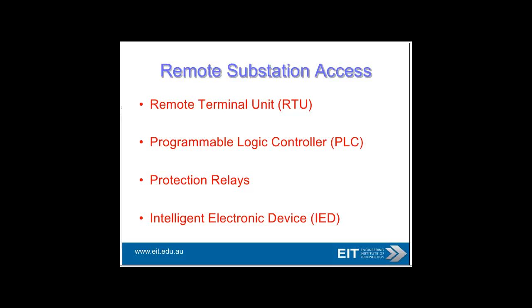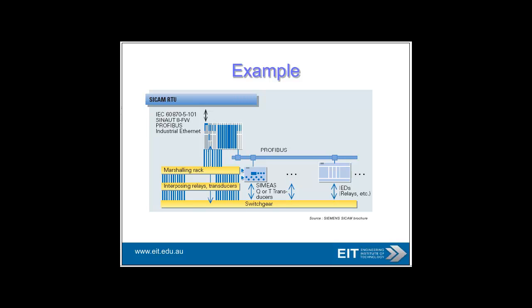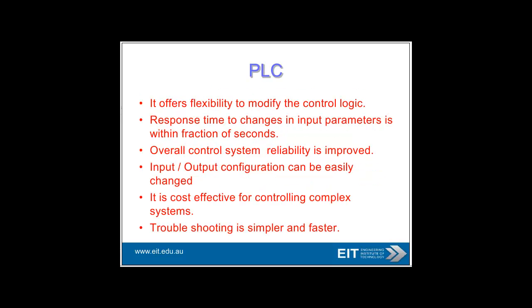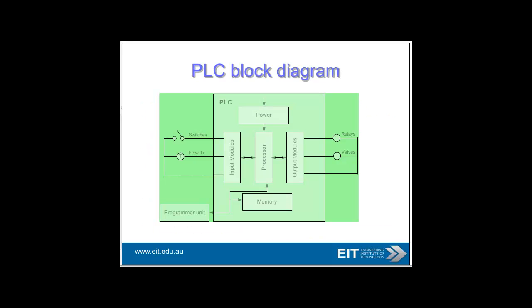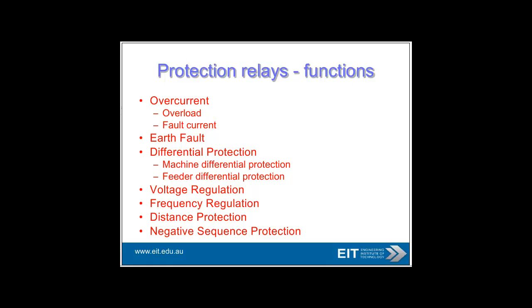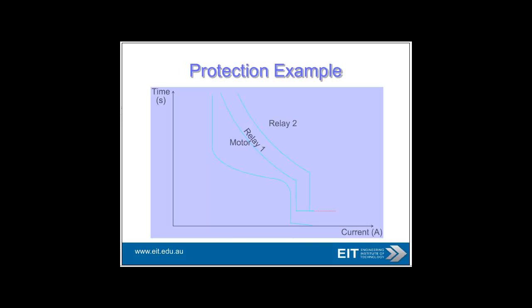From a more practical point of view, you often hear about RTUs, PLCs, protection relays, and IEDs — intelligent electronic devices — with a lot of overlap between them. Remote terminal units are one example. A relay is an example of an IED. A remote terminal unit could really be a PLC — a very flexible device, often programmed using ladder logic. Protection relays are another critical part of the substation, ranging from overcurrent to earth fault and distance protection — all very interesting topics.